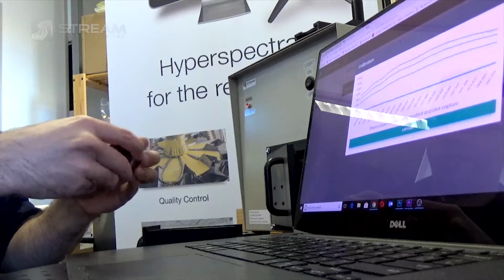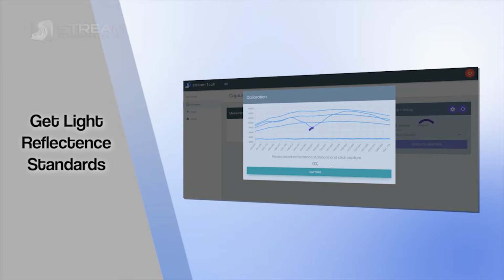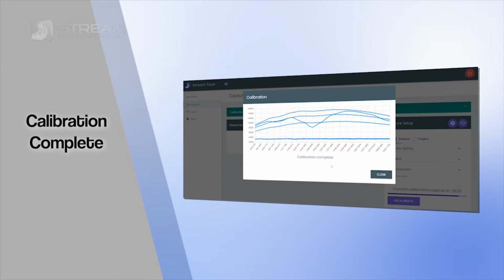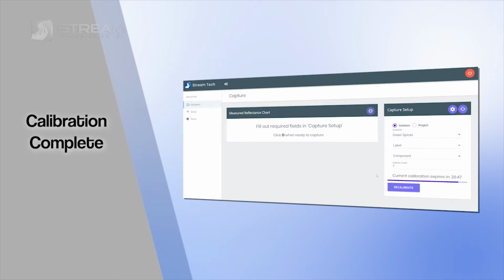Lastly, it asks you to insert a wavelength standard. The wavelength standard basically allows us to calibrate for any differences in measured wavelengths of the spectrometer, and it's also another LabSphere standard. LabFlow will start doing the math on basically the calibration that has to be applied to all your scans to keep them consistent. And now the calibration is complete. And just hit close, and we can start measuring our actual samples.